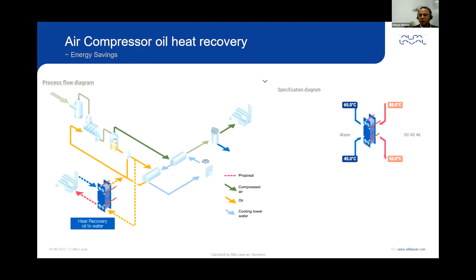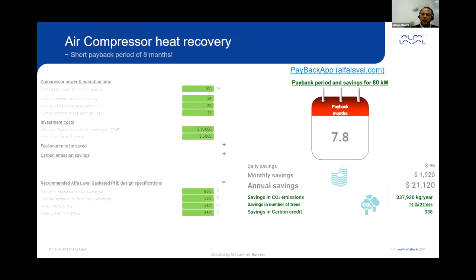Air compressors are another source where we could recover a lot of heat. And air compressor oil is another example of free waste heat which can be recovered and can generate significant energy savings. You will see more of this in the next slide with a payback calculation. So for a 100 kilowatt compressor electric motor, we can effectively recover 80 kilowatts of waste heat. In this particular example, we assume that the compressor operates 24 hours per day, 20 days per month, and 11 months per year. The investment cost for the heat exchanger is $10,000, and the installation cost around $5,000. This gives us a payback period of only 7.8 months.